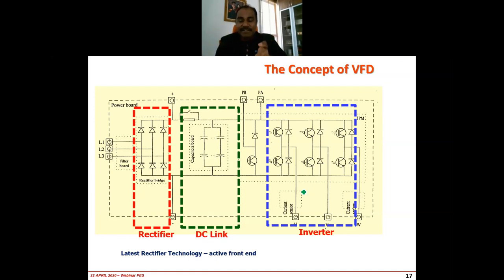So you need to be able to justify it. If you just install a VFD and you are not sure there is going to be a saving, please don't install it, because not only will you see no savings, you will see an increase in maintenance costs. Since a variable frequency drive is completely an electronic system, just imagine an electronic system in industry with all kinds of environments that are very hot, with very poor ventilation, very dusty, a very harsh environment. This electronic system can have a lot of failures and a lot of downtime.